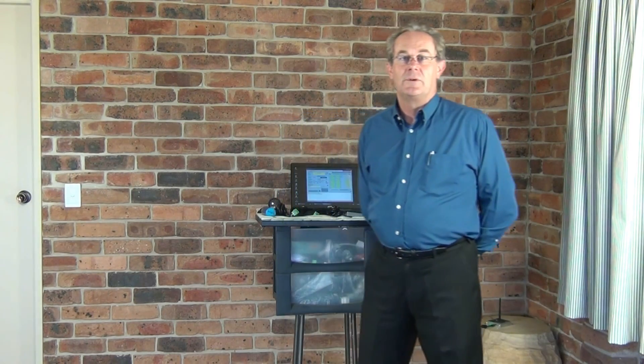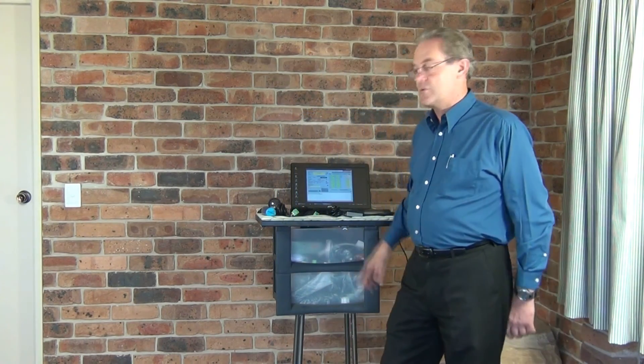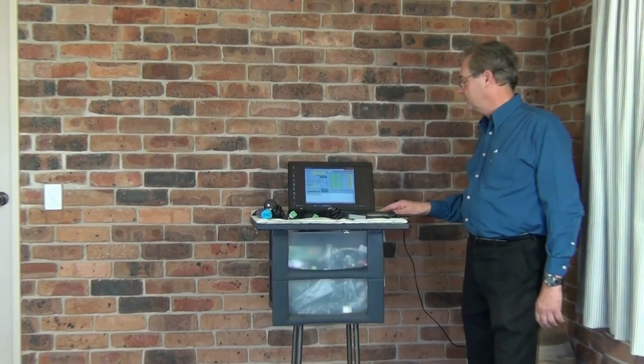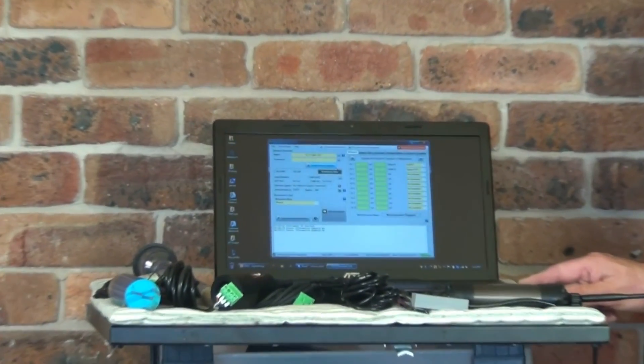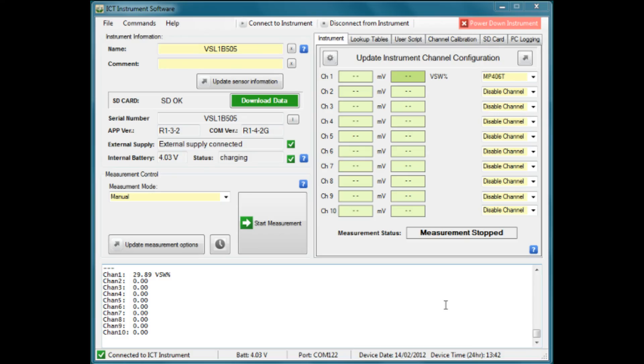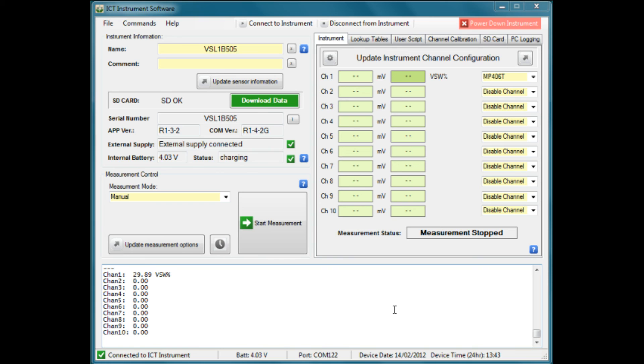In this video, we'll look at the process involved in calibrating an individual channel of the ICT instrument to a known reference. We will take a particular sensor that's connected to the instrument and place that sensor into a standard or reference point, take a measurement, and then calculate a calibration factor that we will use to calibrate the sensor.